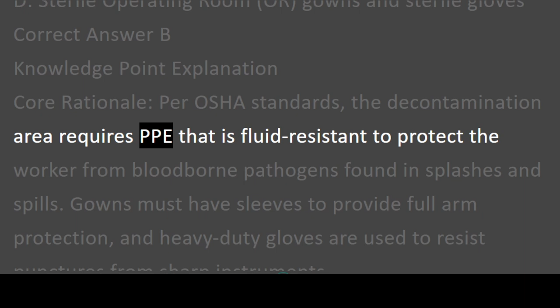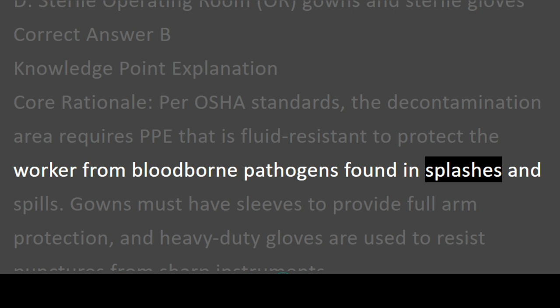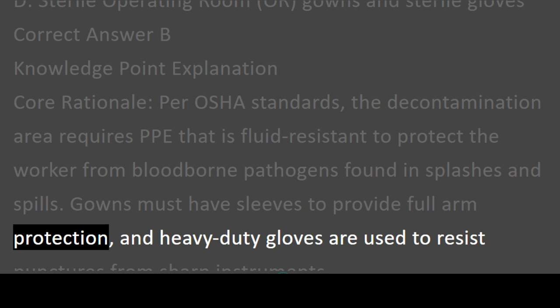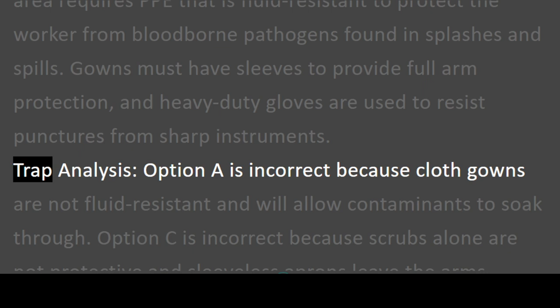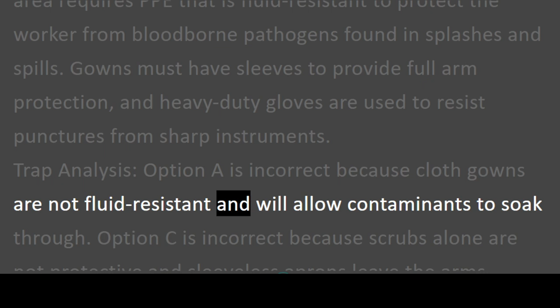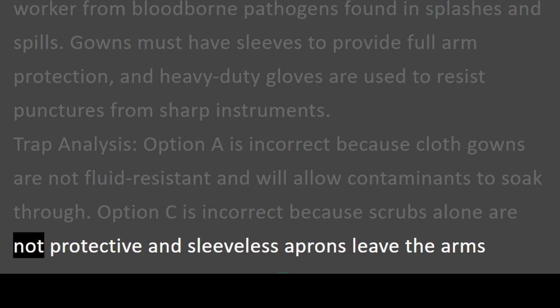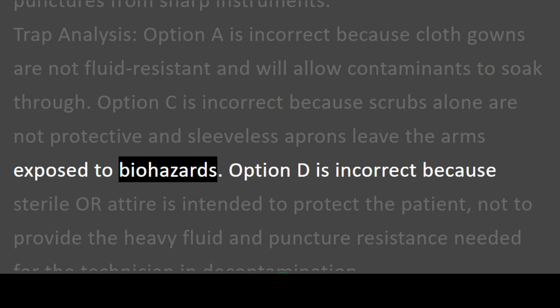Core rationale. Per OSHA standards, the decontamination area requires PPE that is fluid resistant to protect the worker from bloodborne pathogens found in splashes and spills. Gowns must have sleeves to provide full arm protection, and heavy-duty gloves are used to resist punctures from sharp instruments. Trap analysis. Option A is incorrect because cloth gowns are not fluid resistant and will allow contaminants to soak through. Option C is incorrect because scrubs alone are not protective and sleeveless aprons leave the arms exposed to biohazards.